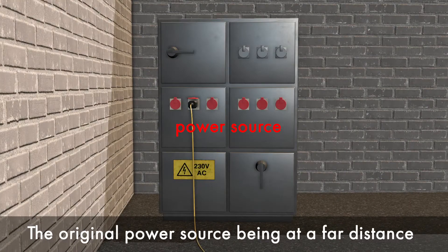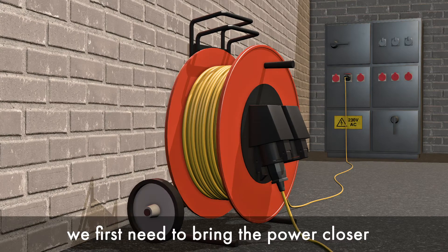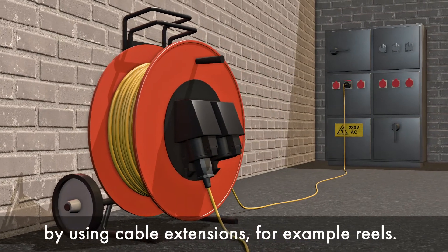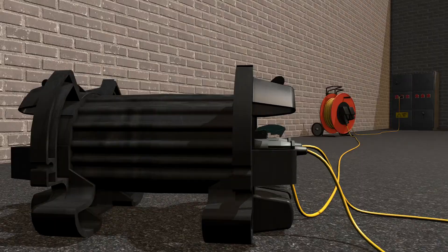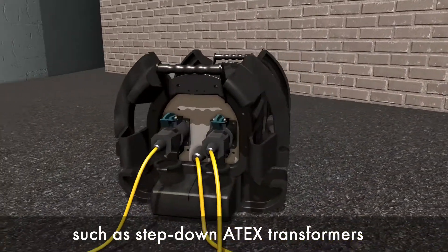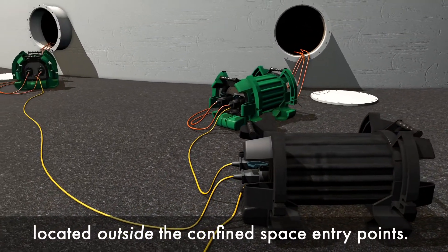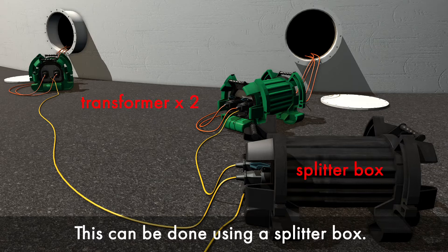The original power source being at a far distance, we first need to bring the power closer by using cable extensions, for example reels. Power must be divided into different devices such as step-down ATEX transformers located outside the confined space entry points. This can be done using a splitter box.